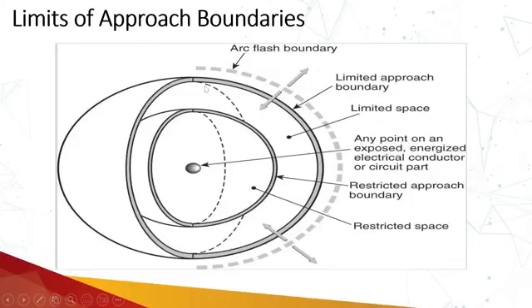Normally, people think that the arc flash boundary is always the outermost boundary, outside the restricted approach boundary or the limited approach boundary, but this is not the case. The arc flash boundary can come within the limited approach boundary, and it can come within the restricted approach boundary as well. And both of the boundaries are independent of each other. The arc flash boundary does not depend on the shock protection boundaries, and the shock protection boundaries do not depend on the arc flash boundary.